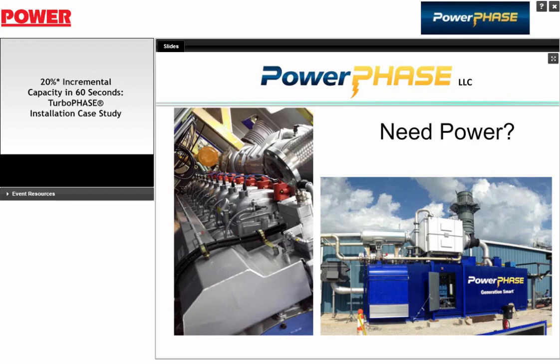All right. Another question here about Turbophase. So Turbophase comes in one size, and you buy as many as needed based on the size and quantity of gas turbines served. Sounds like 5 Turbophase units needed for a single 7FA. Can you speak to that? Yeah, that's true. We're making a production, I call it a production blue box. It's 8 feet wide and 32 feet long, and it's a production system, and it works on literally every gas turbine in the world, 20 megawatts and higher.